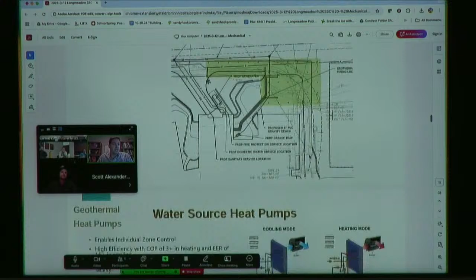Space conditioning throughout the facility is via water source heat pumps. They utilize a refrigeration cycle to provide heating or cooling, and they have an air coil, so it's an air-based system. All the individual water source heat pumps are connected to the same water loop. What that means is that any individual heat pump can be in heating mode or cooling mode at any given time.